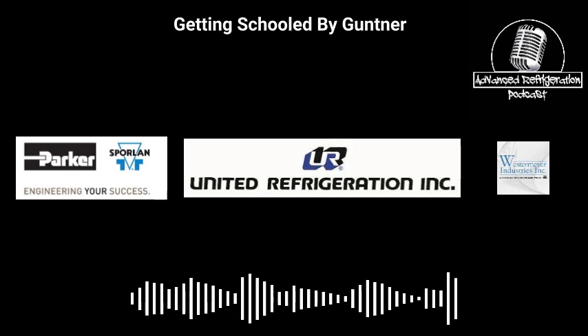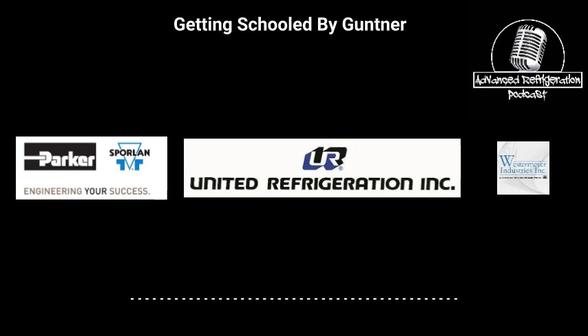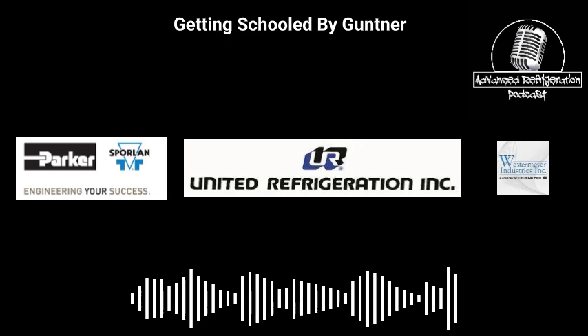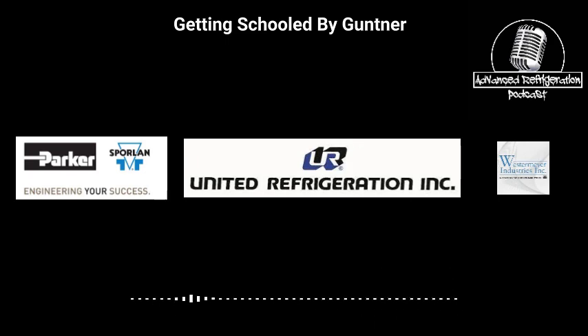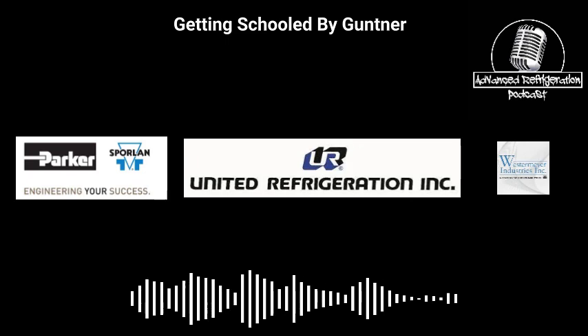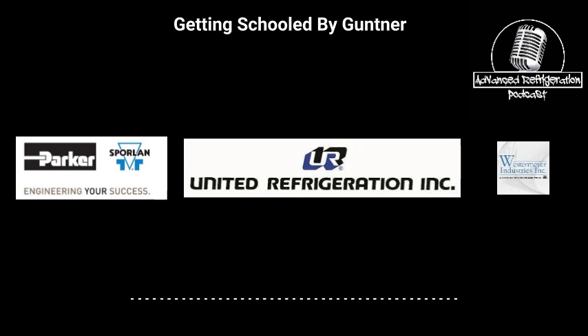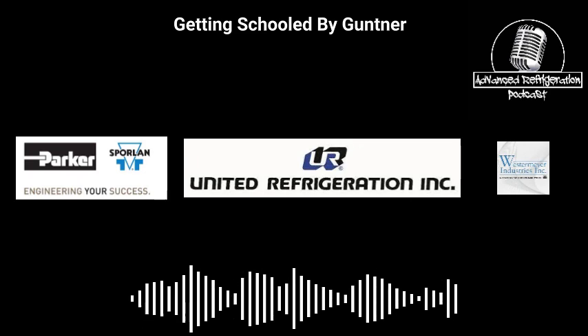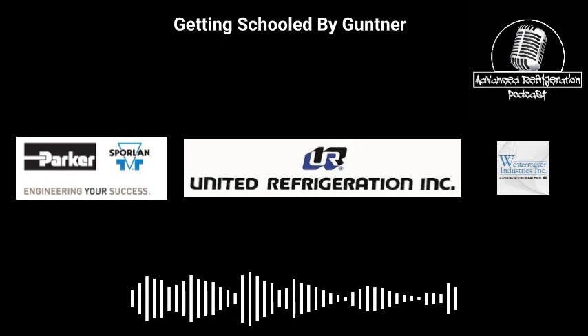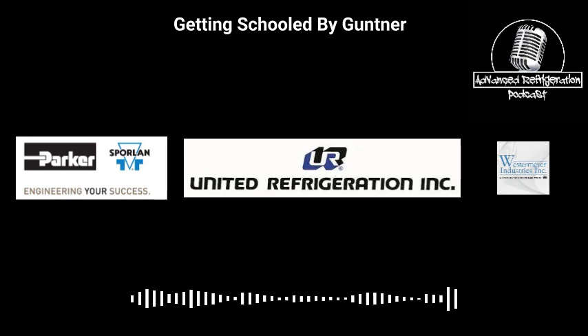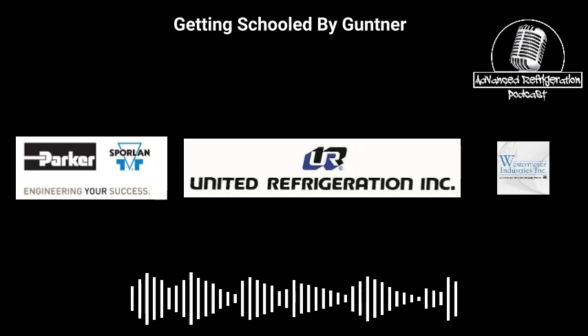The other thing that's nice about this is what some of our competitors do is, instead of running individual Modbus lines, they'll run one Modbus line and daisy chain it from fan to fan. The reason they do that is because it's cheaper. And then you have to program the controller and address each fan individually. With us, you don't have to do that. It's a little bit more work on the manufacturing side, but on the user end, it's easier because if a fan fails, you just swap it out and it comes alive.